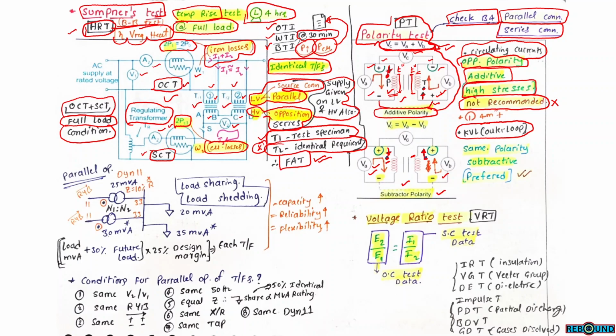So if we take an additional voltmeter VC and apply Kirchhoff's voltage law on the outer loop, then VC equals VA minus VB because primary and secondary will have the same polarities. This is subtractive polarity. This is very much preferred. So during the polarity test, we have to find the polarity of the transformer windings for connections.